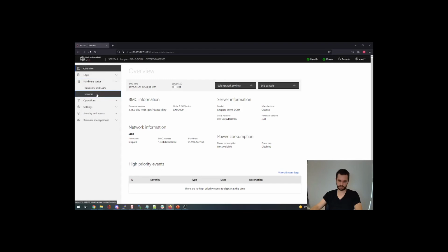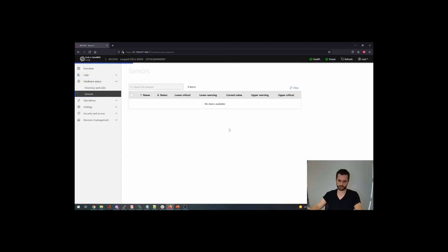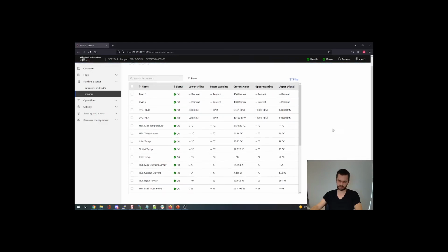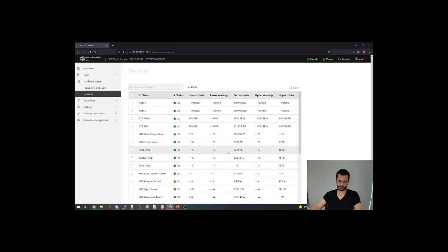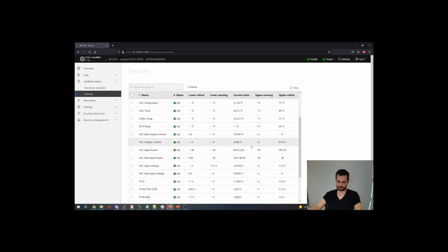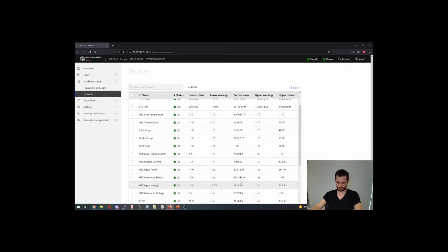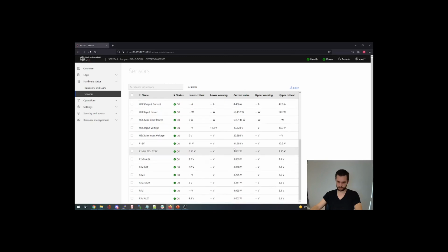Other things around like sensors, I will just quickly go through it and show you a bit about Serial over LAN and Redfish. So it's getting all the sensor information, so you can see the inlet temperature, outlet temperature, the chipset, maximum temperature it's ever reached. This is not really reliable, it has to get another scale factor, but for the ID, you see the mid plane of the power supply, 12 volts, what upper critical it would have to give a log.